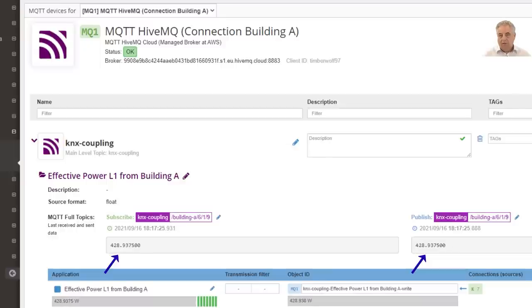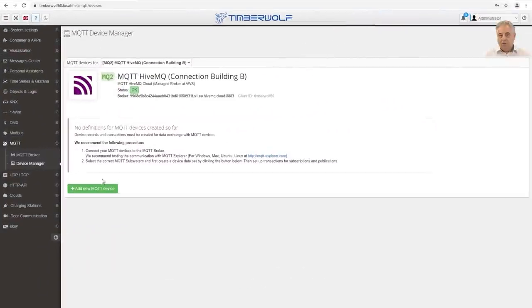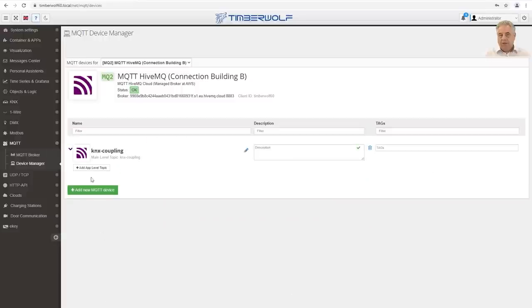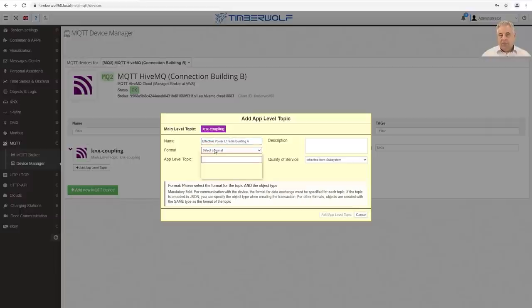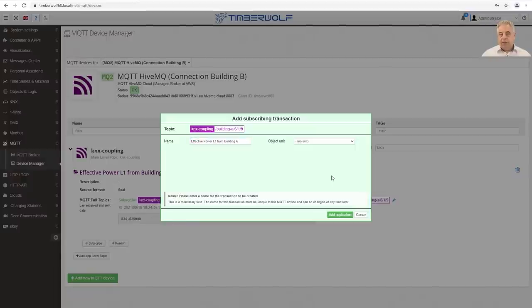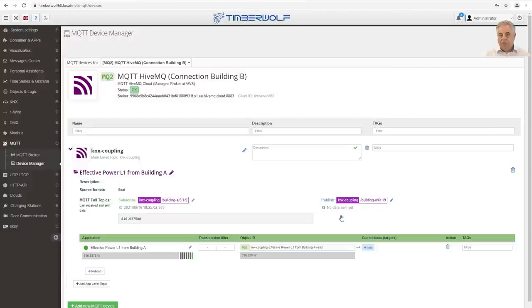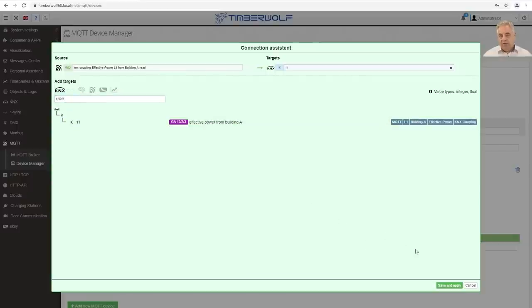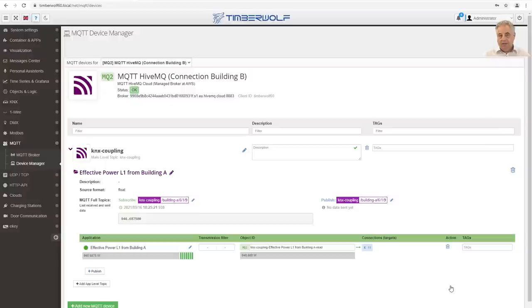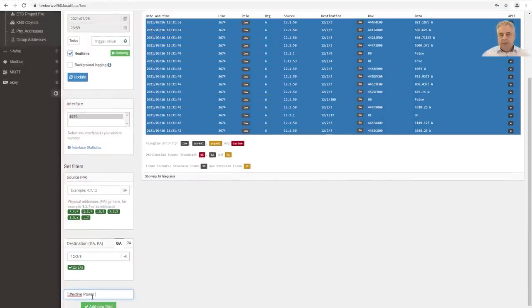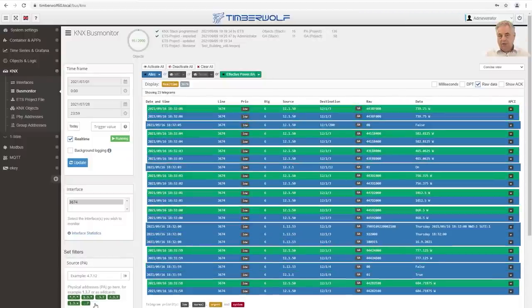Switch to the window with the web app of the second server. The MQTT broker is already set up here, so reception can be created in the MQTT device manager. Create a device entry for the coupling, then the same topic as for Building A with floating point as the data format. The reception of the topic can already be checked in the data monitor. In the next step, create a subscribing transaction — the messages arriving via MQTT, which are already continuously sent by Building A, must now be linked to the KNX object so that these values are also sent on the local KNX bus. To check this, open the KNX bus monitor, create a new filter entry for the target group address, and the running KNX telegrams are displayed in the telegram window according to the filter setting.